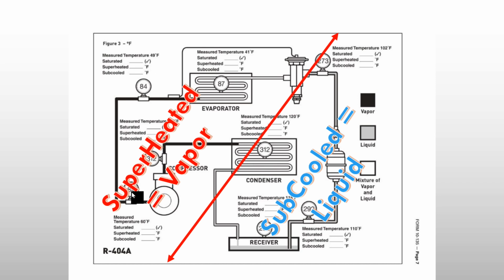And there are even subcoolers that will go inside cases and refrigeration cycles to help. Even though it's superheated suction gas, this suction gas is already cool. It gets colder than the liquid going into the case, and sometimes they'll use that as a heat exchanger. That's why they'll take a liquid line and braze it to a suction line, so that it transfers the heat from the warm liquid line to the cooler suction line, and in doing so they get some subcooling in the process.